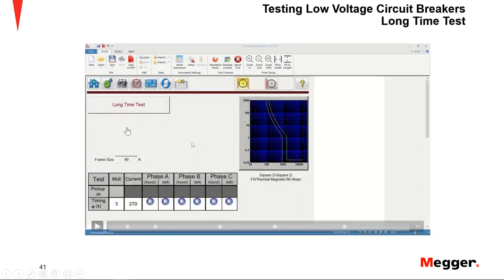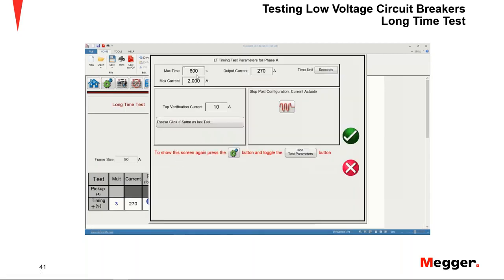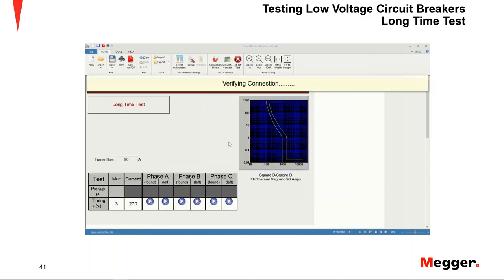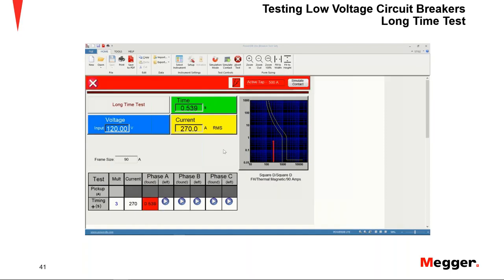We're gonna start with the long time test. And again, notice that the frame size is selected. The test current is also already filled out automatically, which is 3 times my rated current. I'm gonna start with phase A. This screen is for me to review the settings: the test current itself, the tap verification, which the unit will use to detect the tap connected, as well as to measure the impedance of the output circuit to adjust, and give exactly, in this case, 270 amps. So verifying connection, again, is finding the tap, calculating the impedance, and then running the test.